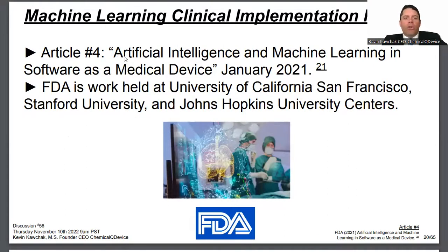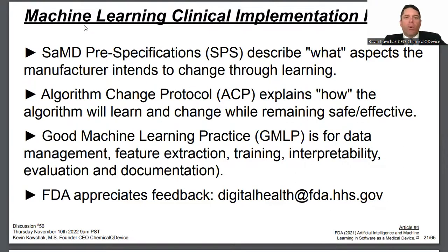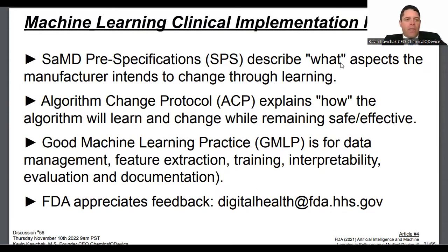Article number four: 'Artificial Intelligence and Machine Learning in Software as a Medical Device' or SAMD, from January 2021, with work done at UCSF, Stanford, and Johns Hopkins. Software as a Medical Device is key. The SPS describes what aspects the manufacturer intends to change through learning. The algorithm change protocol explains how the algorithm will learn and change while remaining safe and effective. GMLP — good machine learning practice — covers data management, feature extraction, training, interpretability, evaluation, and documentation.